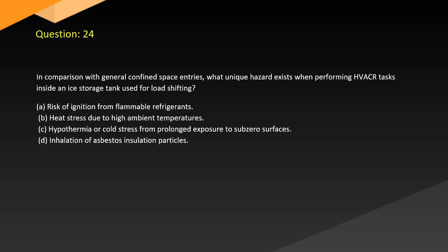Question 24. In comparison with general confined space entries, what unique hazard exists when performing HVACR tasks inside an ice storage tank used for load shifting? A. Risk of ignition from flammable refrigerants. B. Heat stress due to high ambient temperatures. C. Hypothermia or cold stress from prolonged exposure to sub-zero surfaces. D. Inhalation of asbestos insulation particles.